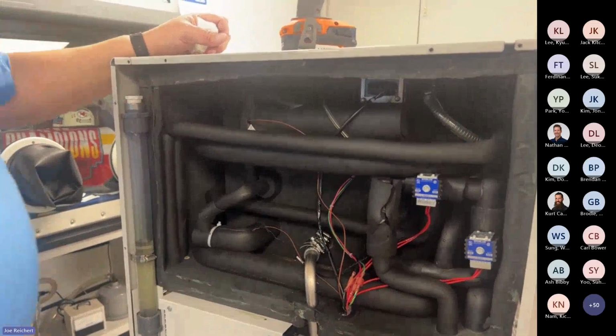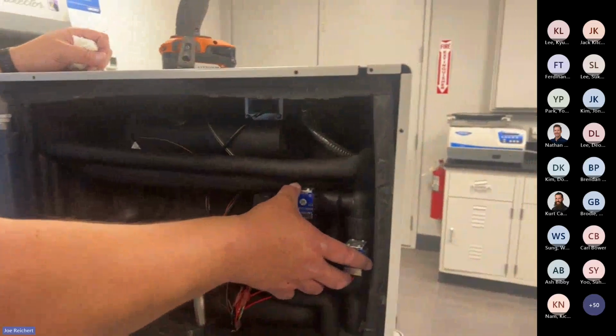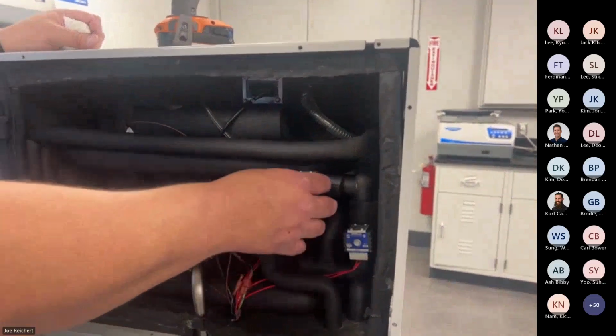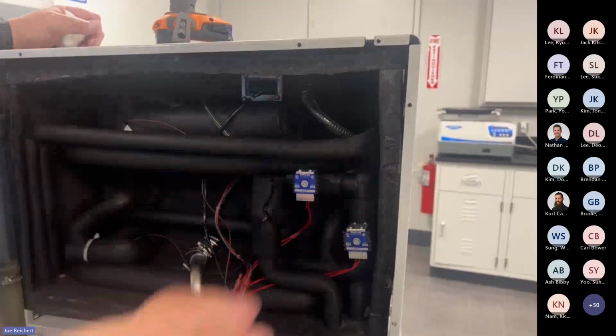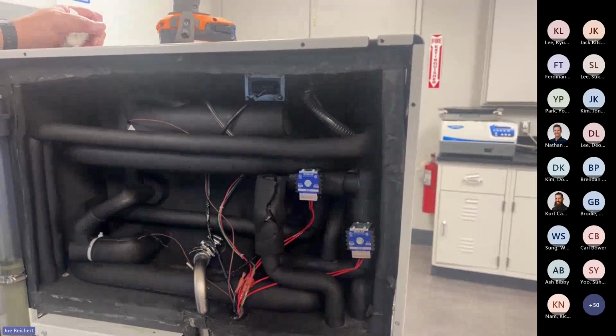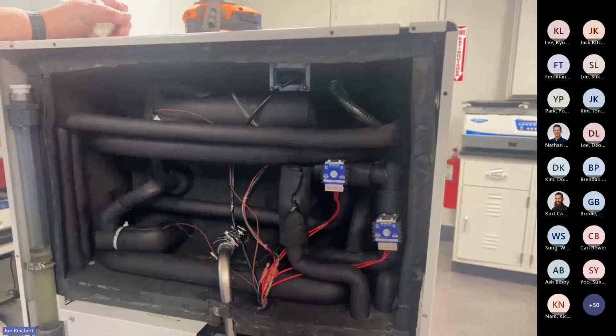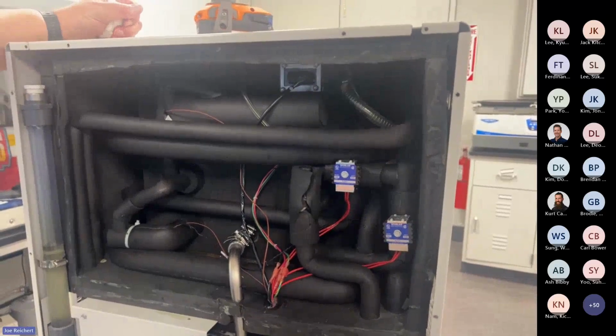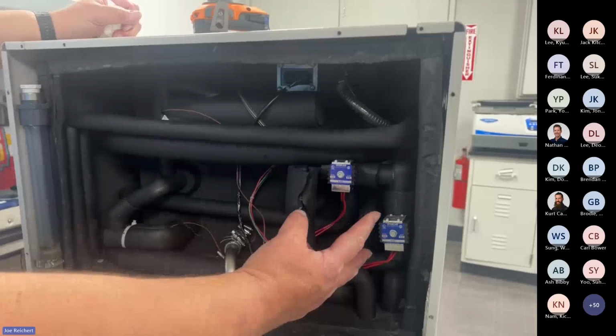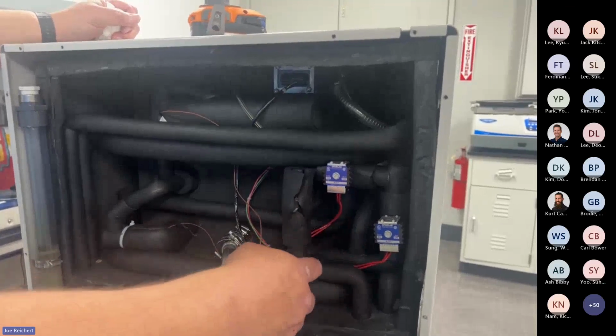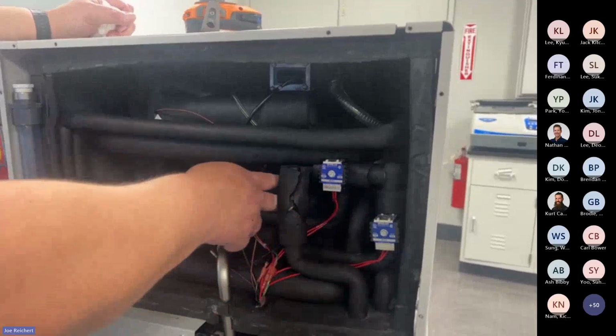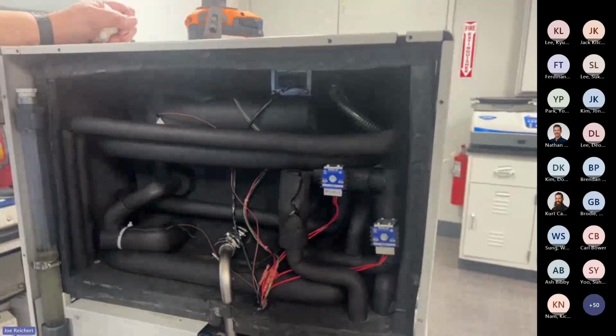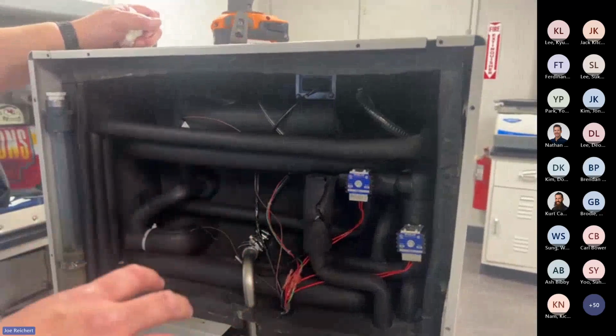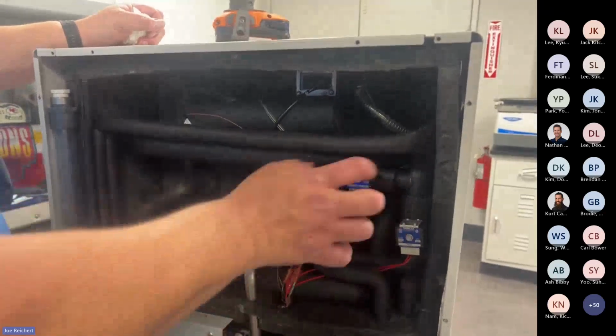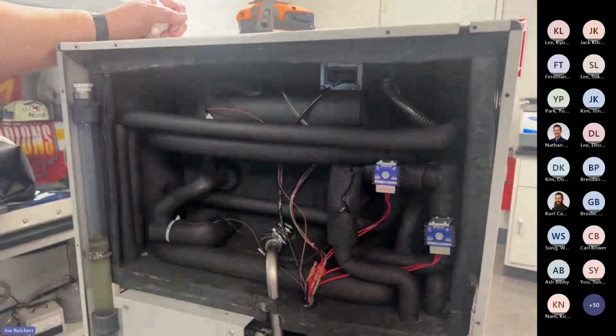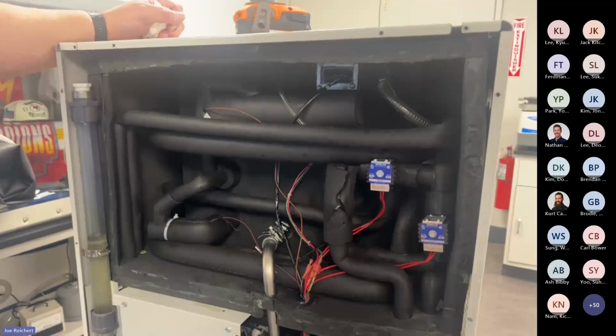You also have the valves here. These valves are not your defrost valves. They look a lot like them, but these are your switching valves. So when you're moving from max cold to a regular mode, like a program, these valves will flip, and that's what changes the gas flow from the collector up to the shelf. And then whenever you are out of max cold mode and the machine transitions into its next segment, the valves will flip back and that'll force the gas to go back down into the collector.